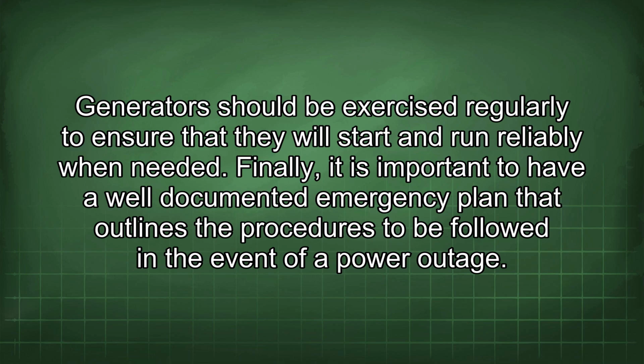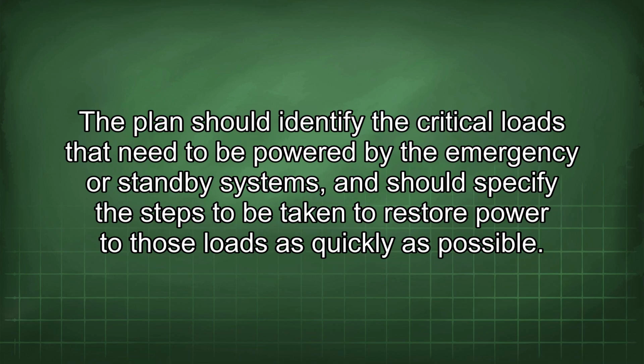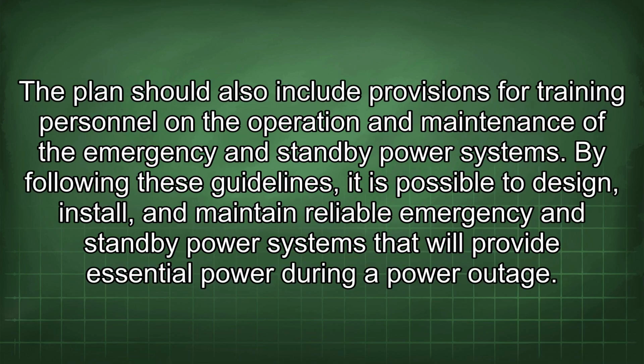Finally, it is important to have a well-documented emergency plan that outlines the procedures to be followed in the event of a power outage. The plan should identify the critical loads that need to be powered by the emergency or standby systems, and should specify the steps to be taken to restore power to those loads as quickly as possible. The plan should also include provisions for training personnel on the operation and maintenance of the emergency and standby power systems. By following these guidelines, it is possible to design, install, and maintain reliable emergency and standby power systems that will provide essential power during a power outage.